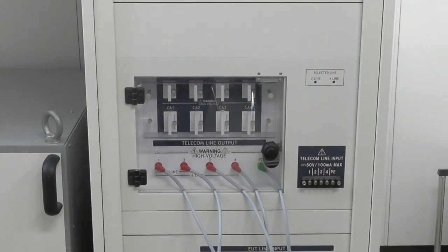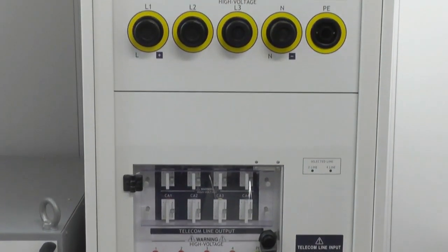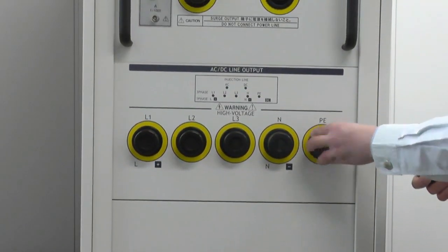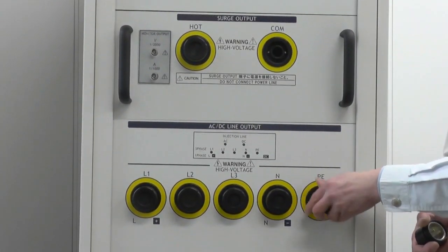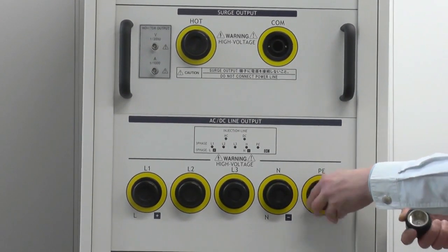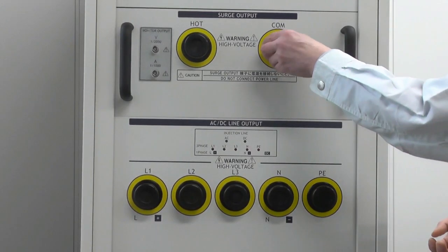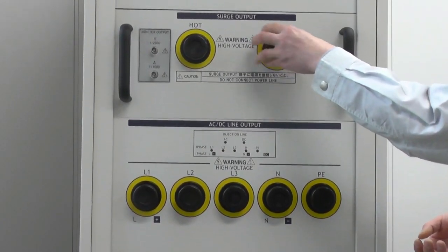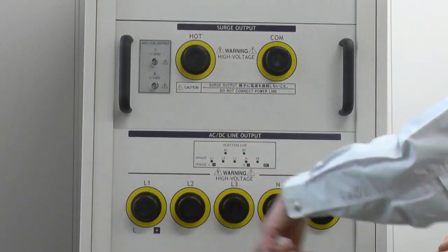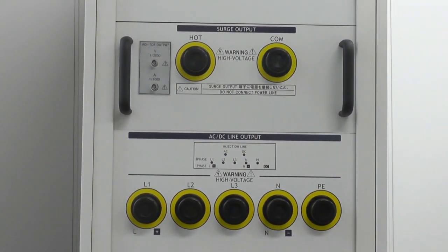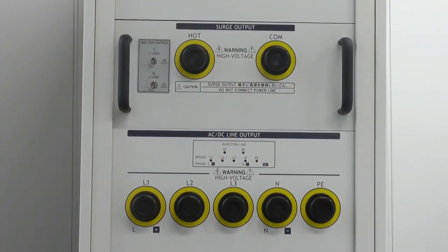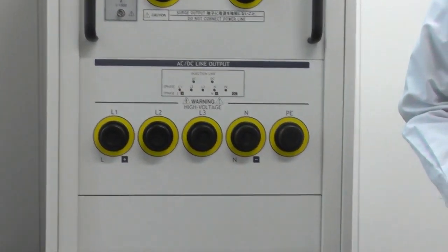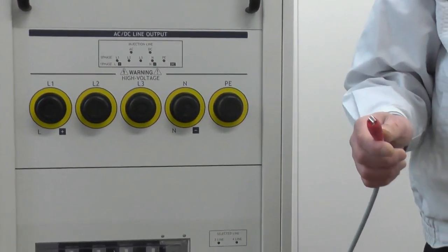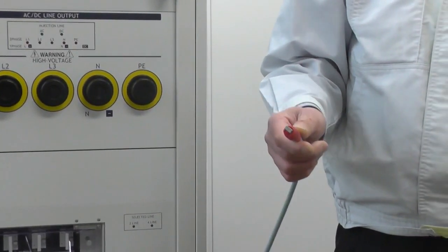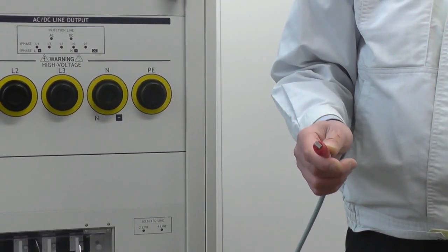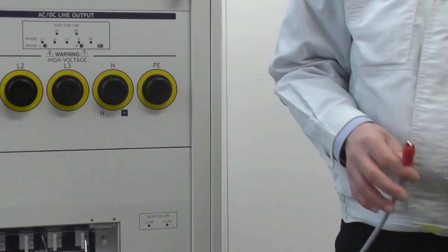In the same way, attach connector caps to the AC/DC line output terminals, as well as the surge output terminals. Be sure to cover all the terminals here. And process the end of the line output cable and directly connect to the EUT. You can safely conduct line surge test.